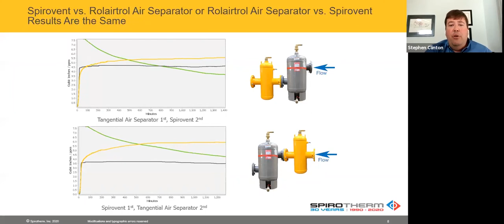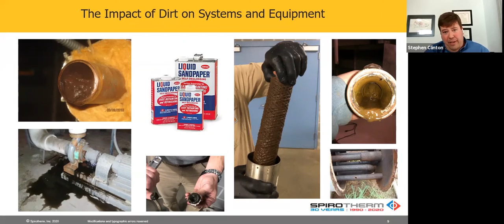Dirt is often, there can be some dirt, literally dirt from a construction site. More often than not, though, the dirt we talk about in systems is metallic debris. That's rust, magnetite, hematite, things like that. That's metallic debris flowing through your system. That's liquid sandpaper. It tears things up. It clogs filters. It messes up pump seals. It tears up flow meters and basically everything else. It causes premature equipment failure.